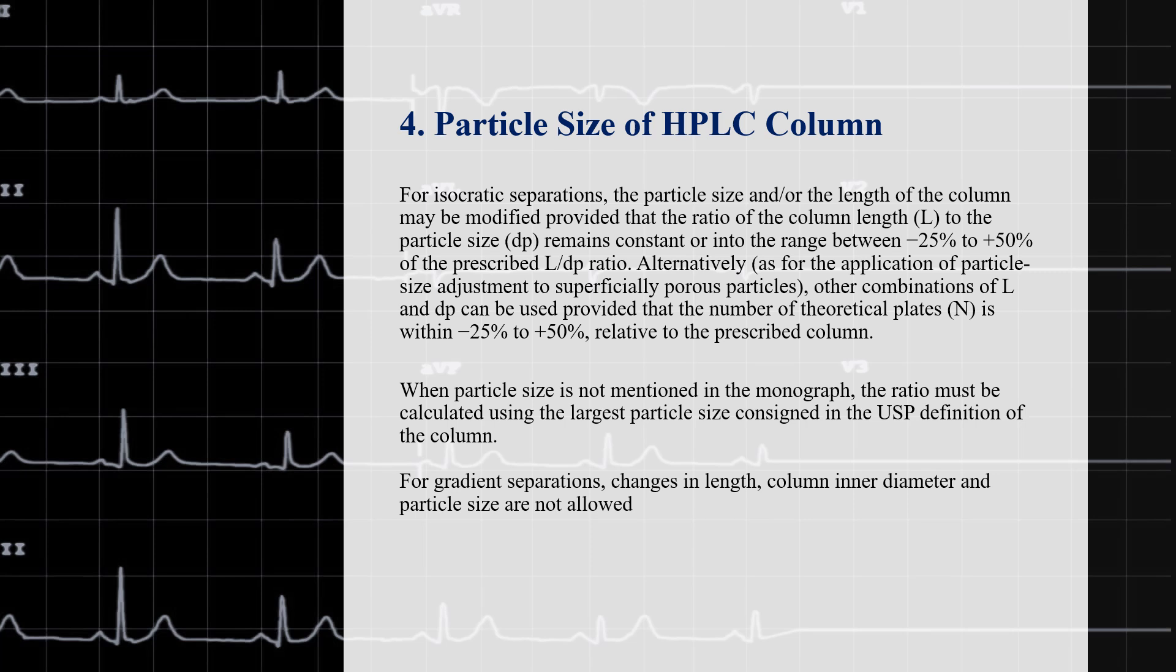Alternatively, other combinations of length to particle size can be used provided that the number of theoretical plates is within negative 25% to 50% relative to prescribed column.